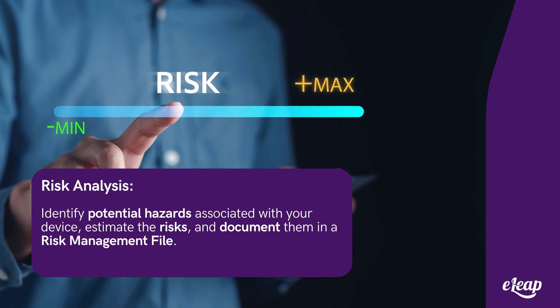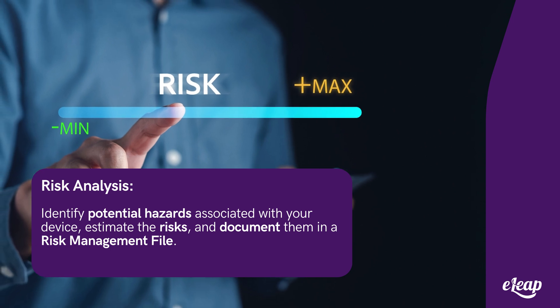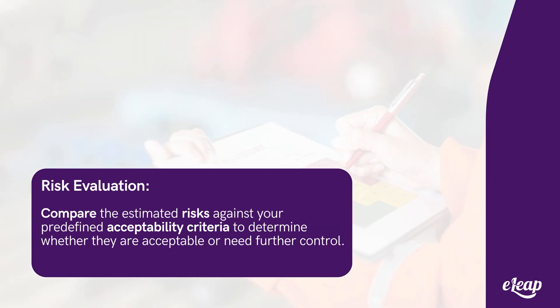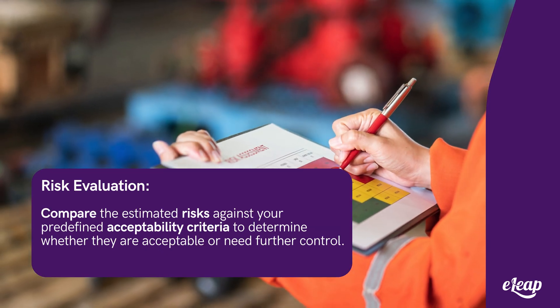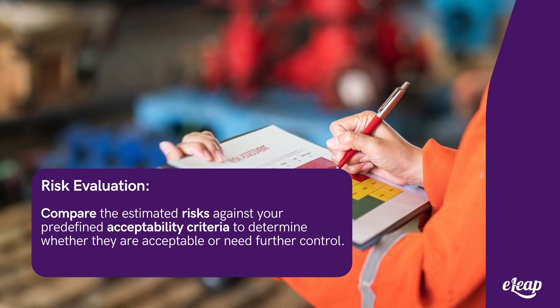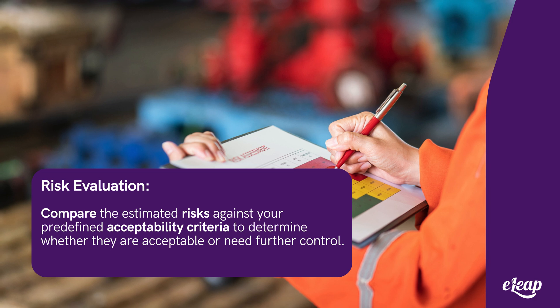Risk analysis: identify potential hazards associated with your device, estimate the risks, and document them in a risk management file. Risk evaluation: compare the estimated risks against your predefined acceptability criteria to determine whether they are acceptable or need further control.